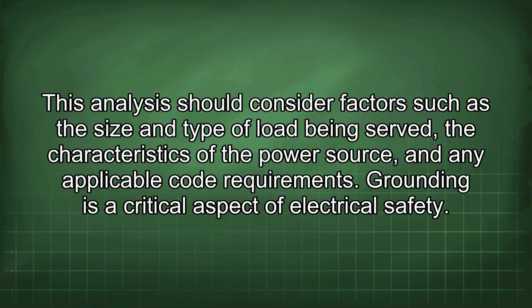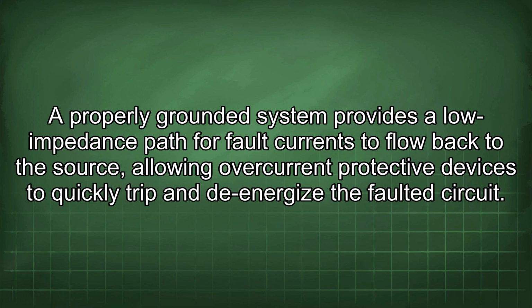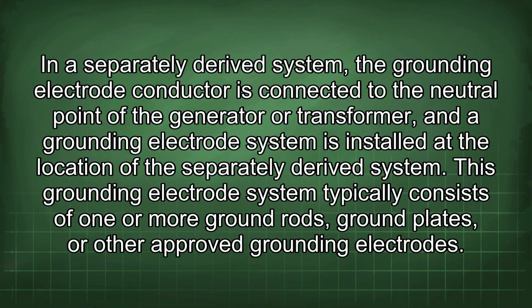Grounding is a critical aspect of electrical safety. A properly grounded system provides a low impedance path for fault currents to flow back to the source, allowing overcurrent protective devices to quickly trip and de-energize the faulted circuit. In a separately derived system, the grounding electrode conductor is connected to the neutral point of the generator or transformer, and the grounding electrode system is installed at the location of the separately derived system.